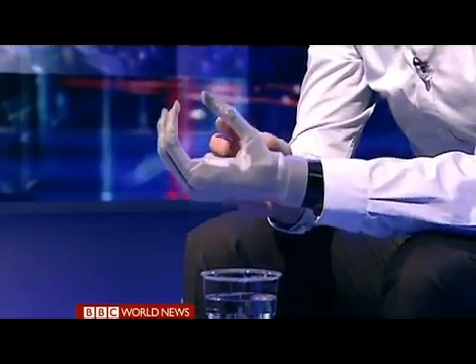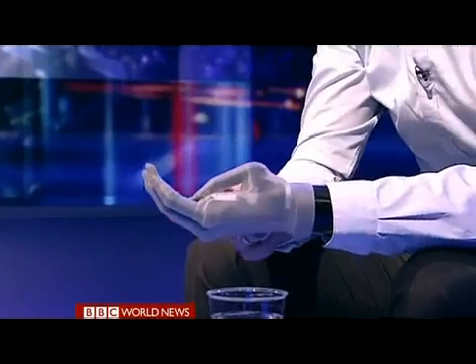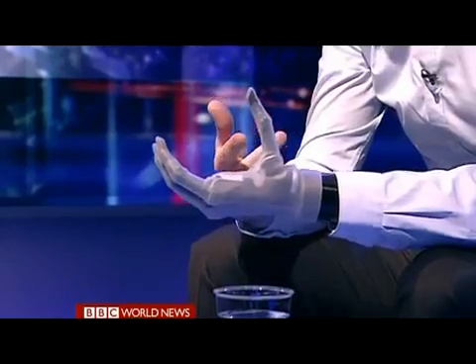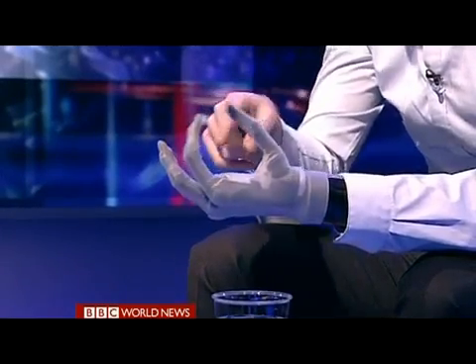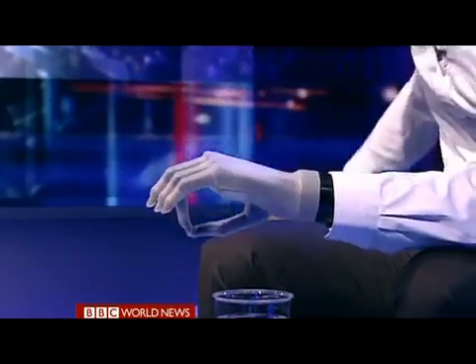Dr. Meyer shows that different control signals produce different grip patterns. For example, you can tell it to park four fingers and only move the thumb, which is very useful for donning and doffing clothing. You can also set it to move only two fingers while the other three are parked, which is very useful for picking up smaller objects such as a pen.